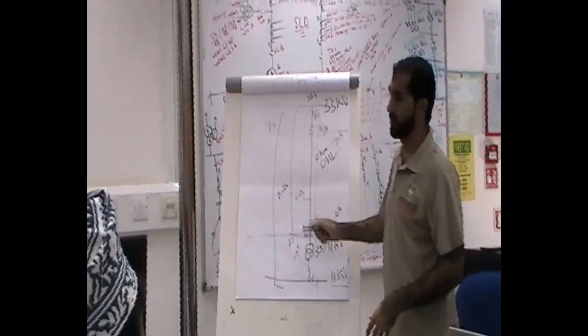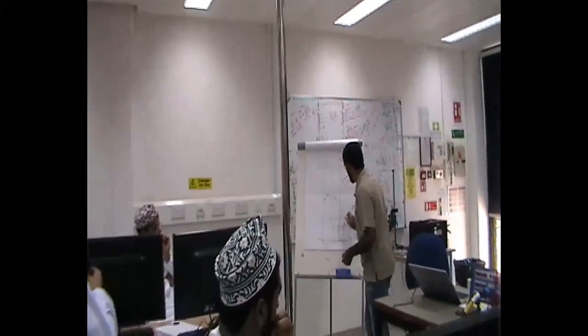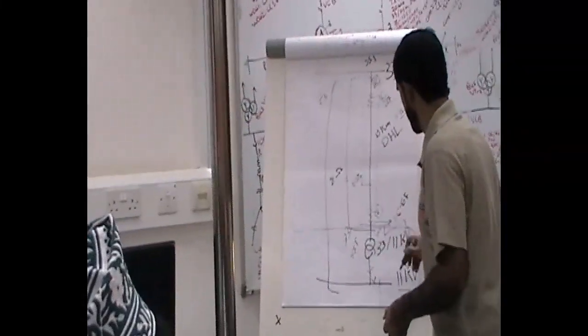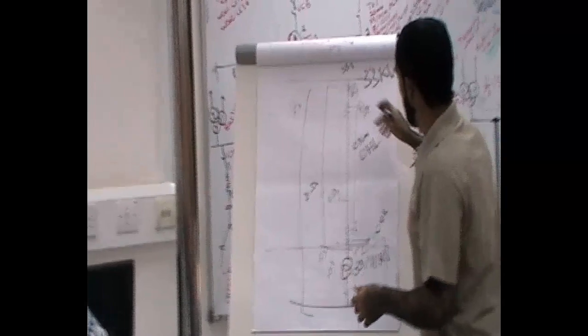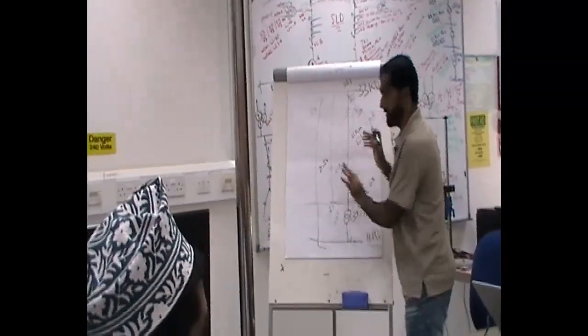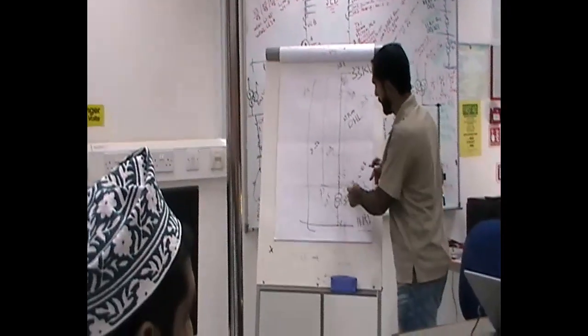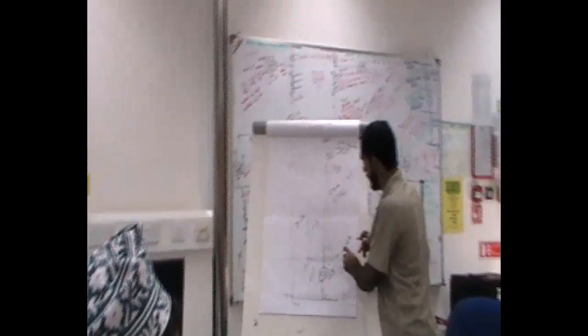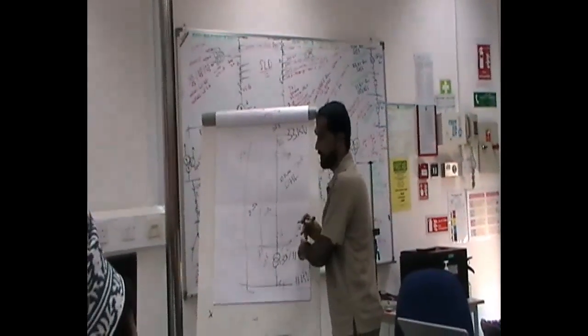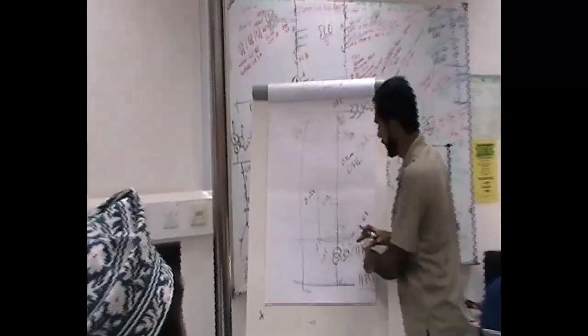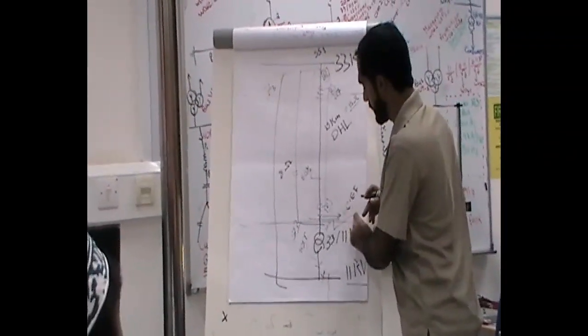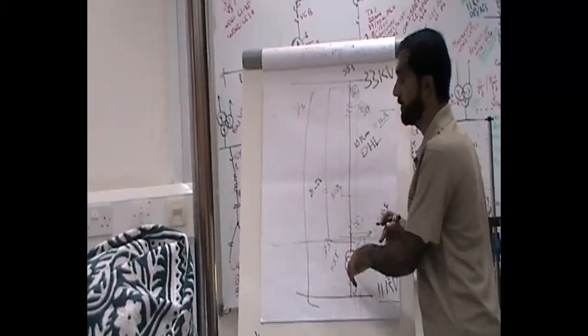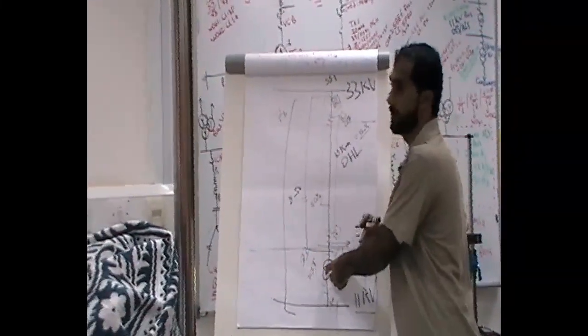So if there is another substation after the line, in case we have another line, sometimes we have a 33 kV bus bar and then another substation. Zone 1 and zone 2 will be the same basically. Zone 3 will be based on the next line. But in this case, if I'm considering this line, the transformer impedance will be higher, so I'll go with the transformer also.